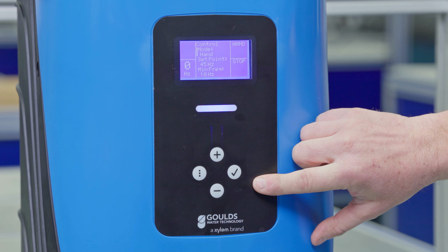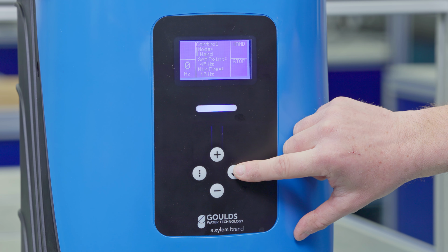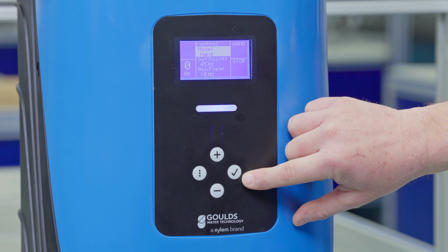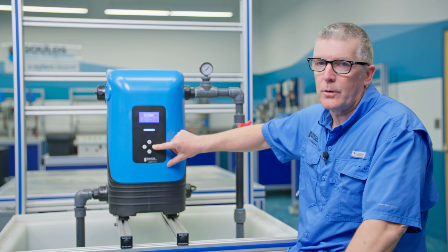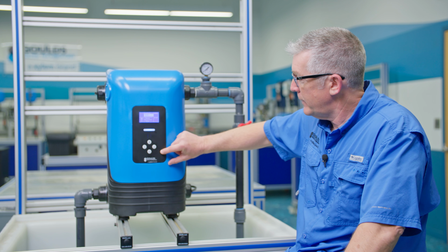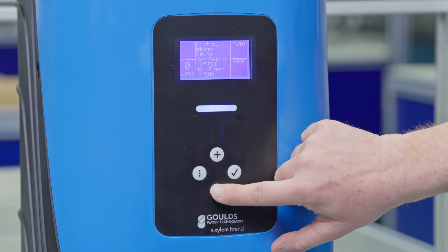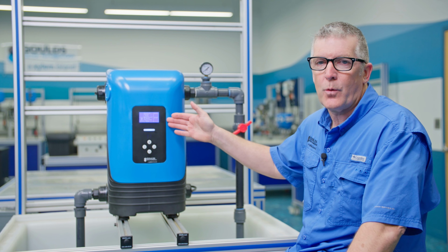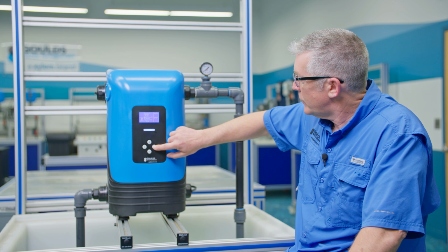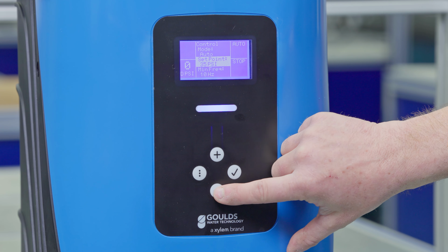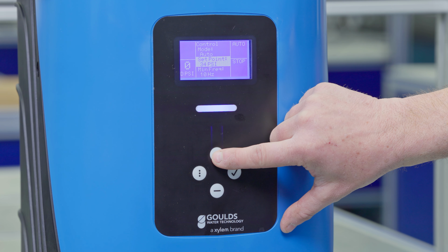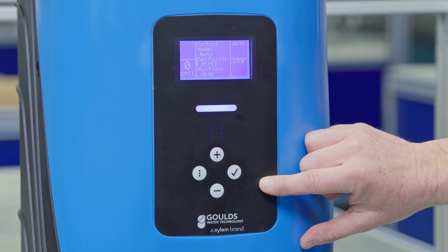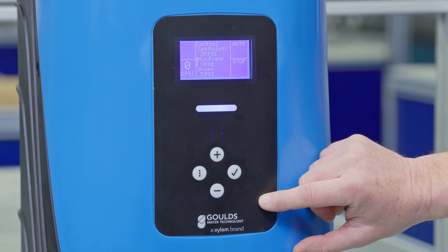We're going to go back into control. And let's change that back to the default, which is looking at the sensor. So again, highlight it. So we're back in auto mode. So again, you got to enter or save. So I'm going to hit the check box. Go down to the next, which is set point. And so we can change the set point here in the menu. And again, simply highlighting it and then hitting the increase or the decrease buttons for that. And just remember, you got to save it. We're going to hit the check box here, and let's go on to the next one.